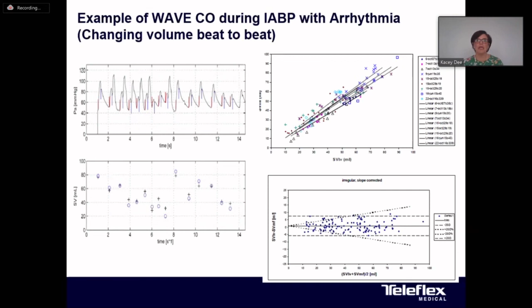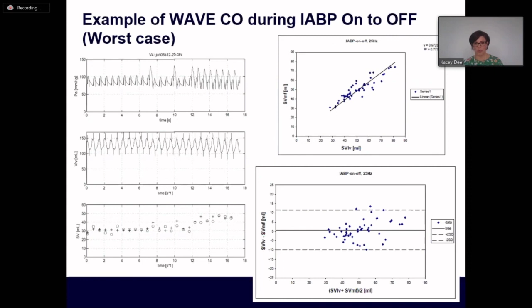Now, this slide shows the same information as the prior slides, but now we're going balloon pump off to on. And this is where we saw the biggest abrupt change in our volume. And this is when we can see here that, again, the algorithm calculates stroke volume accurately, but follows the changes in stroke volume. And the accuracy of the measurement during the abrupt change in volume when we initiated therapy, that change in volume was plus 11 to minus 10 mLs or cc's. And this is the widest range of measured to calculated stroke volume that we saw. But once the stroke volume change was stabilized, the accuracy improves back to plus or minus 5 mLs.